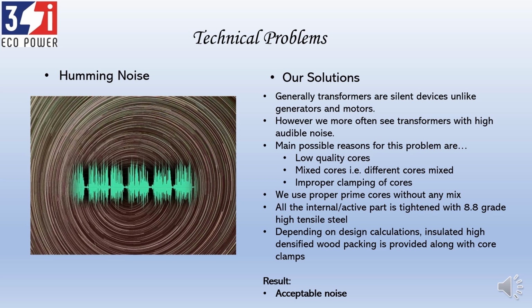And how? The main reason for generating noise is the magnetostriction of the cores. During magnetic induction of the cores, the magnetostriction effect comes into play, and because of this effect, noise is generated. It will be more with low-grade CRGO steel or a mix of CRGO steel, which I was mentioning in earlier slides. To get the no-load losses, some suppliers mix cores. We don't do that. By not mixing, and using proper prime CRGO material, this can be contained.